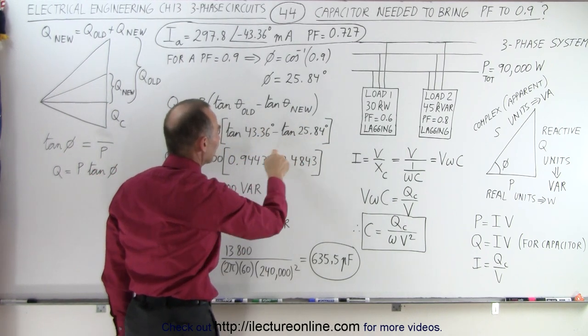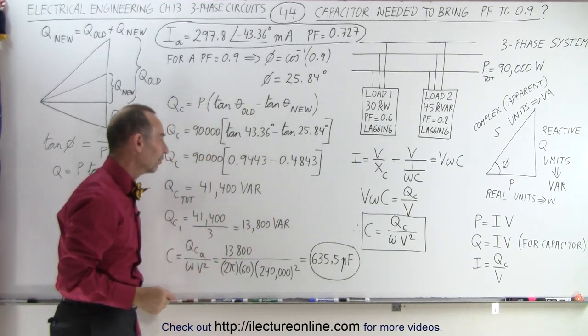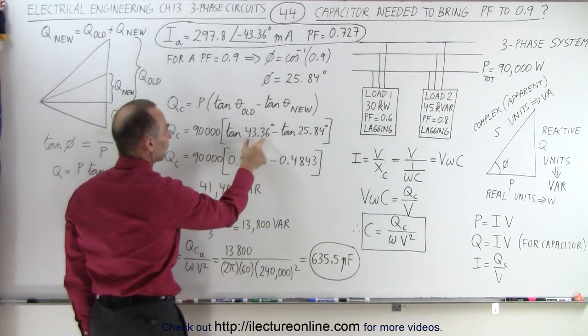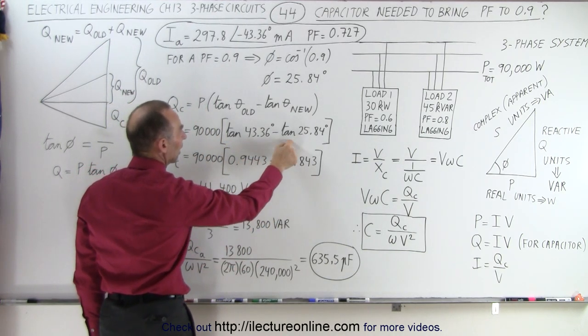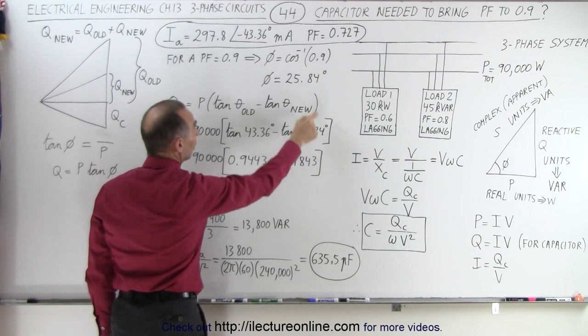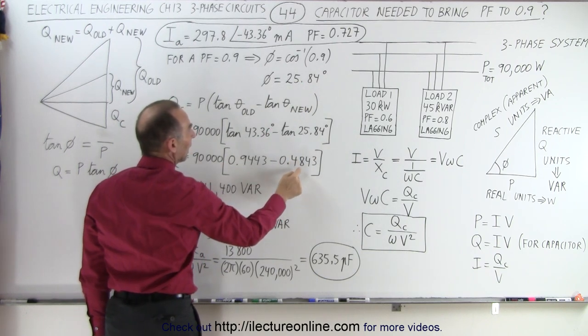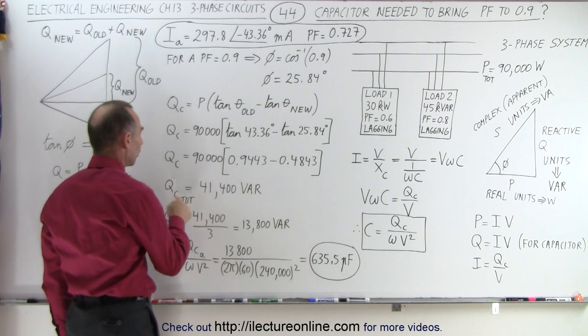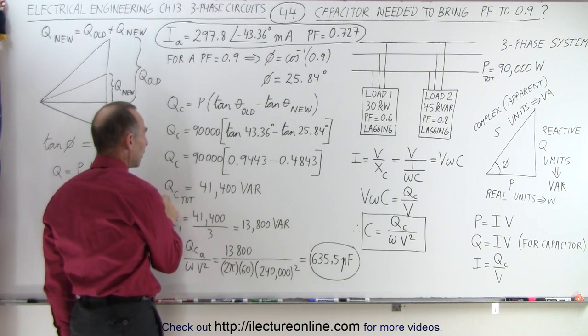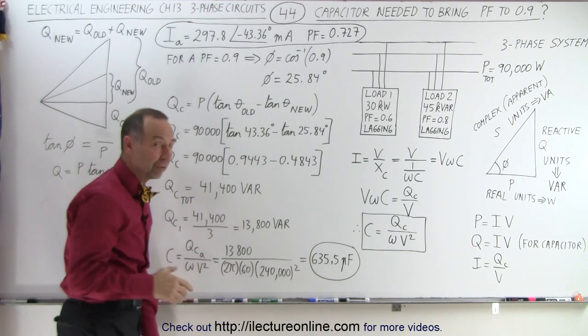We want this to be a positive value, so we use positive angles to see the difference. Notice we go from the tangent of this, which is almost 1, minus the tangent of the new phase angle we want for a power factor of 0.9, and so that equals this. In other words, the total reactive power of the circuit is 41,400 VAR.